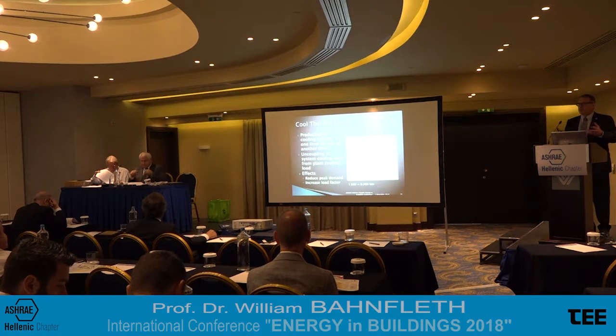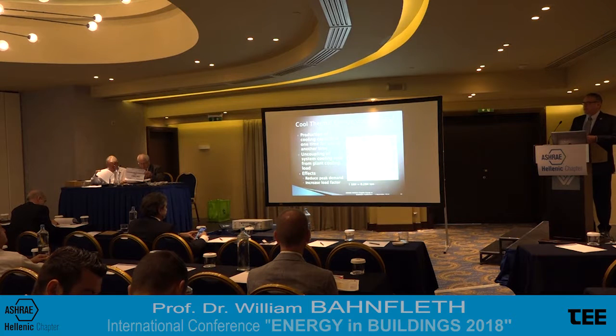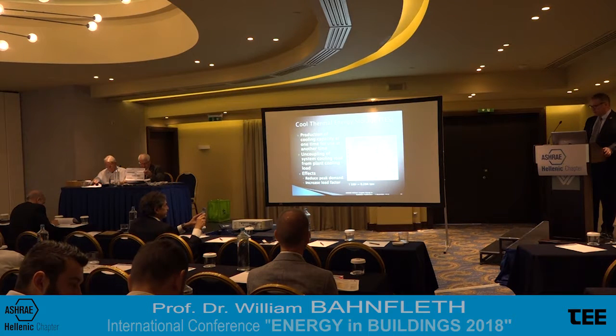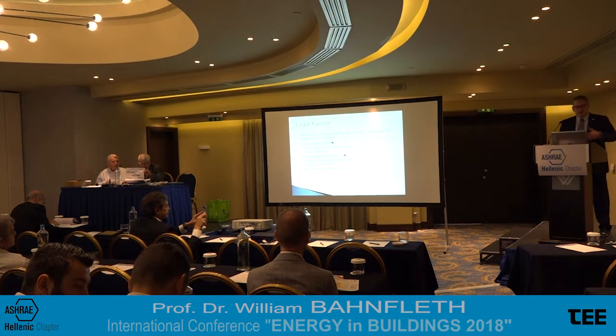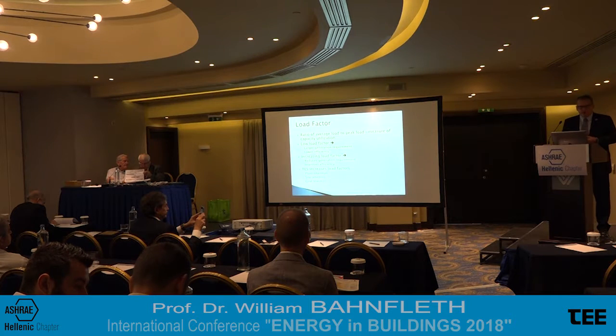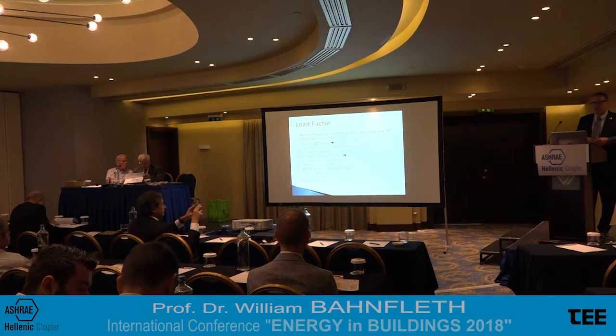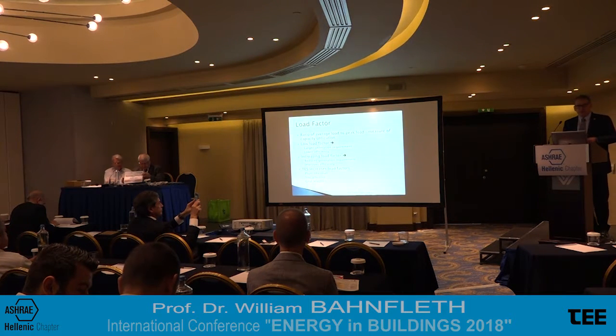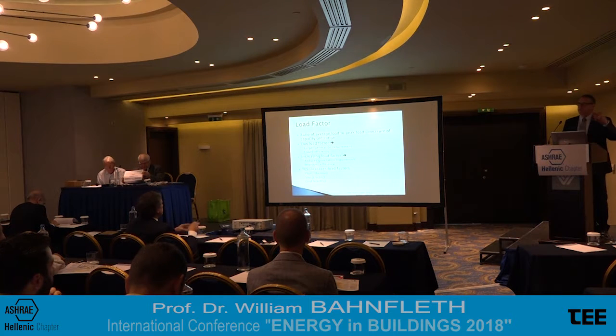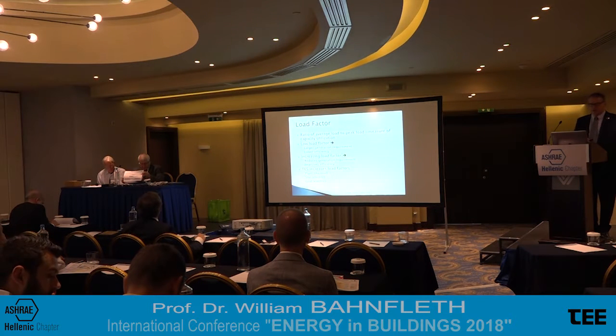The things that it does are primarily reduce peak loads, so it makes equipment smaller, and it also increases load factor on that equipment, which is also generally associated with cost effectiveness and efficiency. So that's a good thing. And in case the load factor is not a familiar concept, that is simply the ratio of an average load to a peak load. Could be a thermal load, could be an electric load.